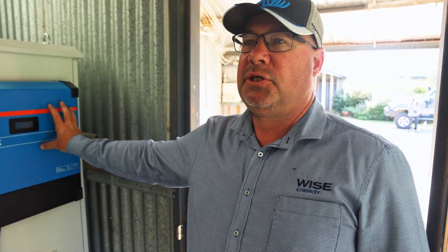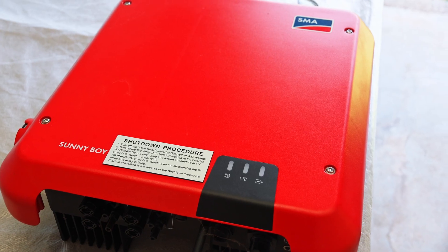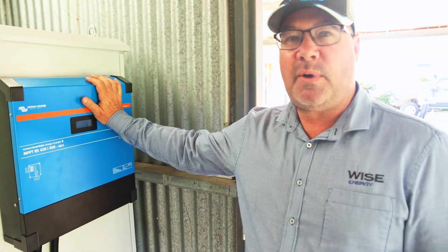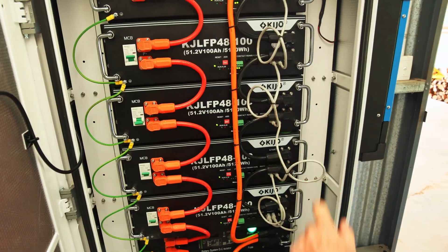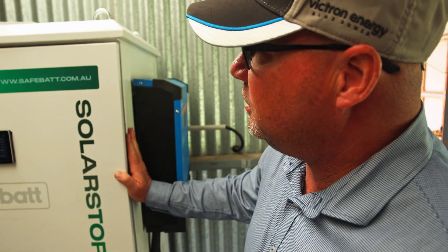The advantage of changing over to a DC coupled solar charge controller, as opposed to an AC solar charge controller — they both have advantages and disadvantages — but for example if the grid goes out and your battery goes flat, this particular inverter will not start back up. With DC coupling, as soon as the sun comes back out this one will start back up and start charging your batteries. If a battery comes offline, we'll be able to see it both locally on the screen here and remotely, so we can remotely manage the battery system.